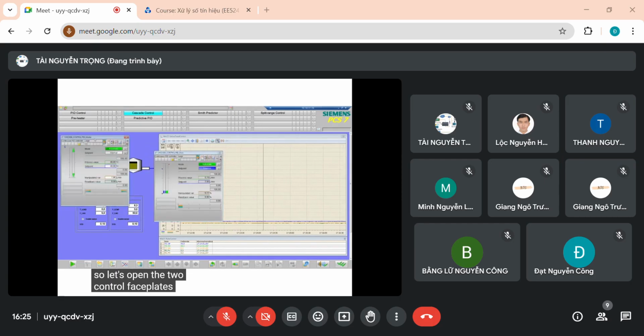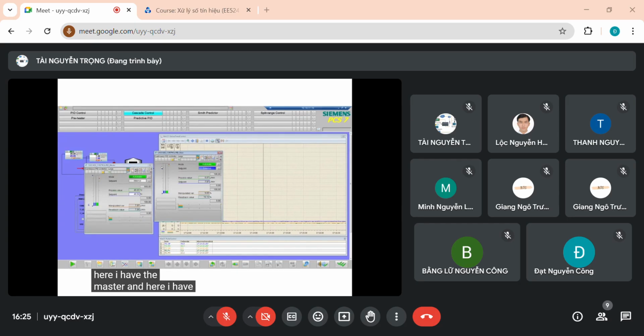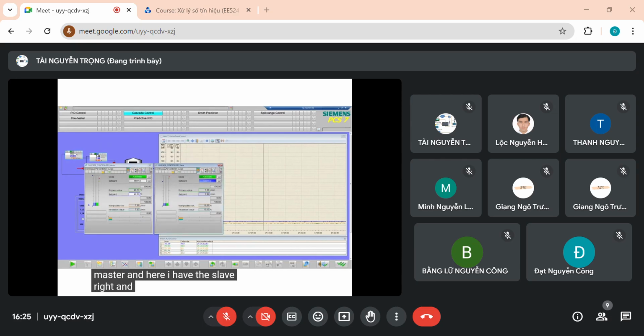control faceplates. So as you can see here, I have the master and here I have the slave, right? And you can see here that the slave controller is in external mode. It is impossible to change by clicking over here the set point of this controller, because this slave controller receives the set point from the master controller. You can see it over here. The manipulated value of the master controller is the set point of the slave controller.